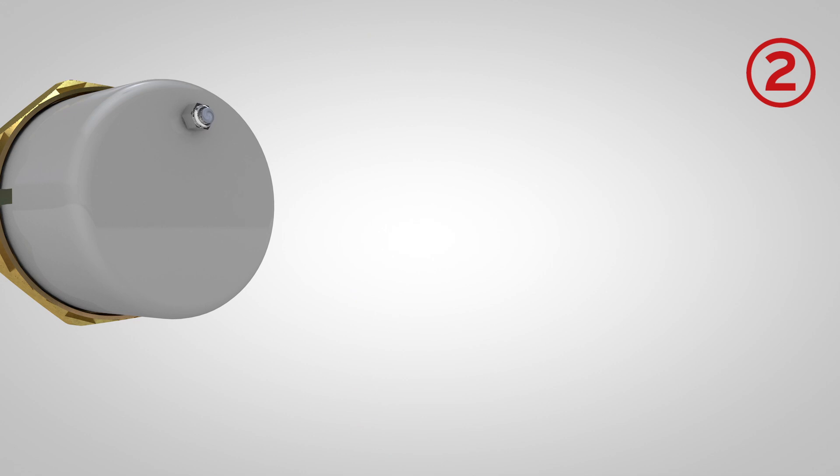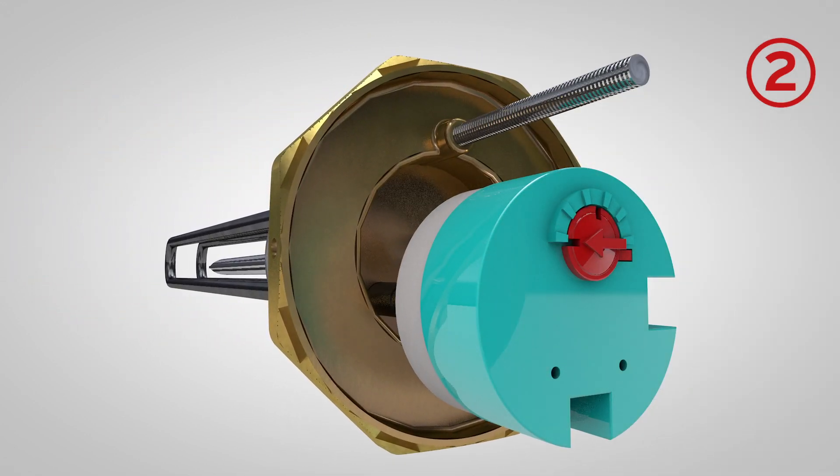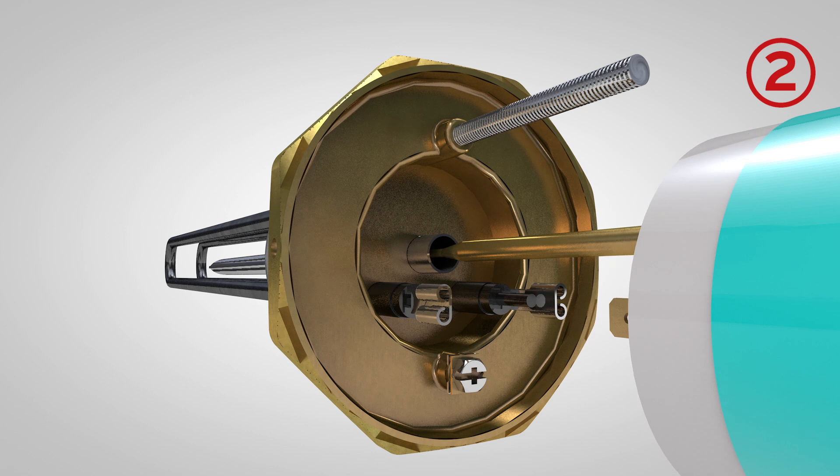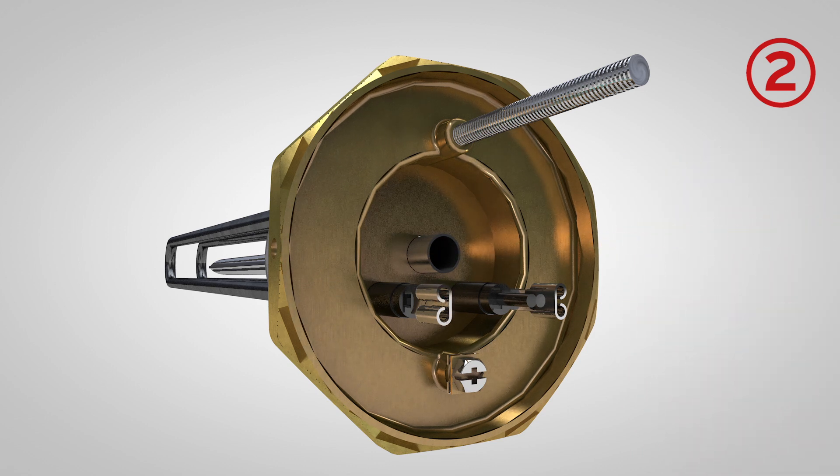Isolate the immersion heater and remove the cap to allow you to fully inspect the heater in situ to try and identify where the leak is coming from. A key point is to check for obvious leaks at braze joints, the thermostat pocket and the brass body itself.